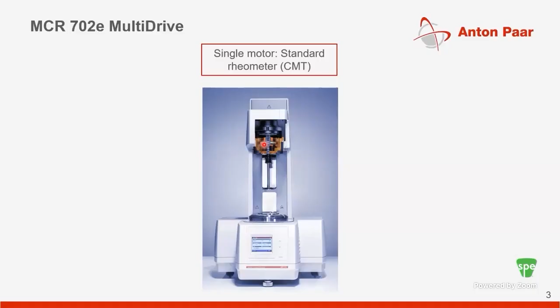You then calculate torque from this motor current, so you don't need an independent torque sensor — all rheological parameters are calculated from it. You also have an optical encoder, from which you can calculate things like strain rate, which can then be transformed into rheological properties. This traditional device can use different temperature devices and all the other accessories in our general portfolio.